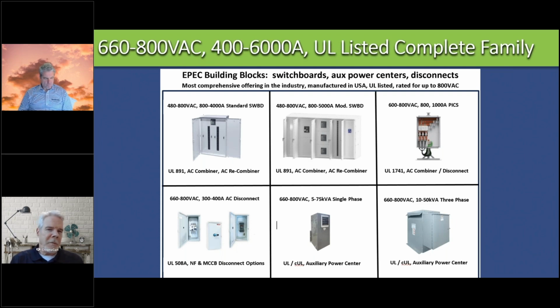so again, full UL891. We also released another product this January, and that is the top middle. We call it our modular switchboard, developed really for 800 volt when you need a recombiner function. With this switchboard, you can have a main breaker up to 5,000 amps, and you can have feeder breakers that are 800, 1,000, 1,200 up to 2,500 amps as well. So you may have inverters in the field going to a combiner and then coming back into a recombiner. We can do that as well with this chassis.